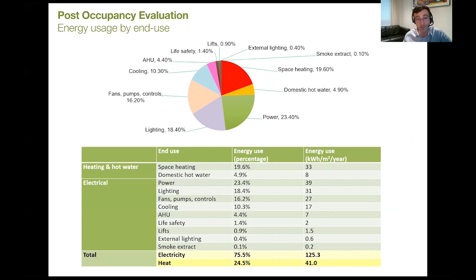It boiled down to some headline figures. As I mentioned at the start, the figure of 700 kilowatt hours per meter squared for the heat - we didn't feel was a representative benchmark, so we used the CIBSE benchmark instead for heat, which was 240. But even off that more conservative benchmark, the building was using per meter squared 60% less, which is quite a radical shift from where it was - really industry-leading performance for a retrofit.